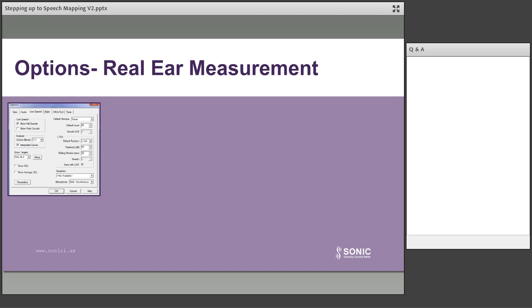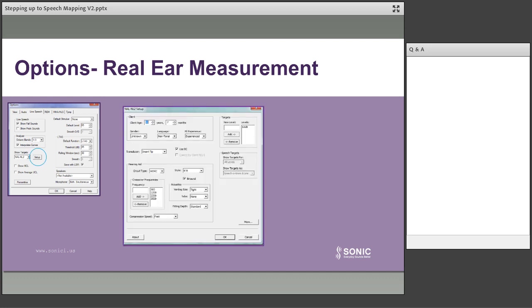Now, when you go into options again, so in your options screen, you go into setup, again, there are a number of parameters. And people get very confused, I think, because not all of these things are going to affect the real ear target. We know that gender does, because we know that males like to have their sound 2 to 3 dB louder than females, so that will affect the target. We know that language will, so the difference between tonal and non-tonal. We know that if you set the levels at new user rather than experienced, that will change the target levels. We know that if you use the air-bone correction factor, that will also affect the target. So it will add a half to a third of the air-bone gap onto the gain, onto the target as well. And we know that the binaural will also.